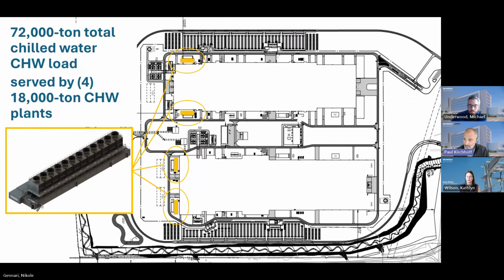From an installation standpoint, these four plants were shipped in phases. The first 18,000 ton plant was on site, started up and operating well before a single 72,000 ton plant would have been running. As the owner got their process equipment installed in parallel, we were able to supply chilled water and get those systems commissioned. Thinking about schedule surety and de-risking a job, that was a big win for the client using this approach.